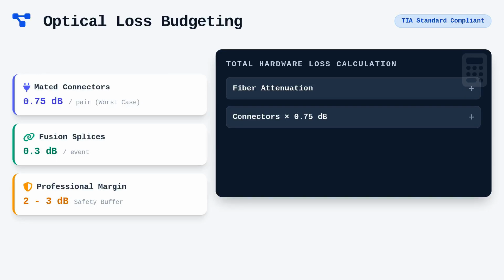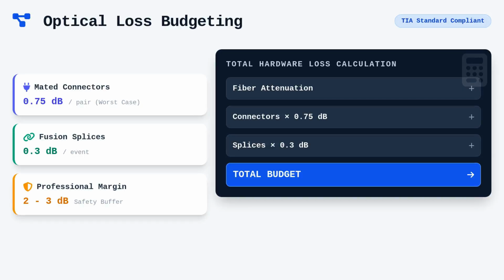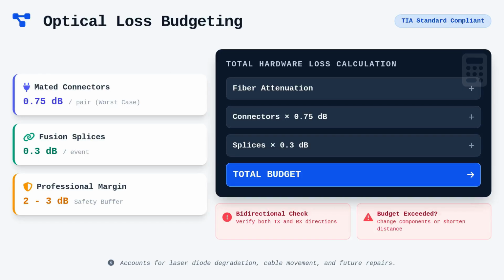It is critical to calculate this budget for both the transmit and receive directions, as fiber properties are rarely perfectly symmetrical across a diverse plant infrastructure. Maintaining a power margin, typically of 2 to 3 decibels, is professional practice to account for future repairs, cable movement, or the natural degradation of laser diodes over several years of operation. If your pre-calculated loss exceeds the equipment's power budget, you must reconsider the component selection or shorten the physical distance between your telecommunications rooms.